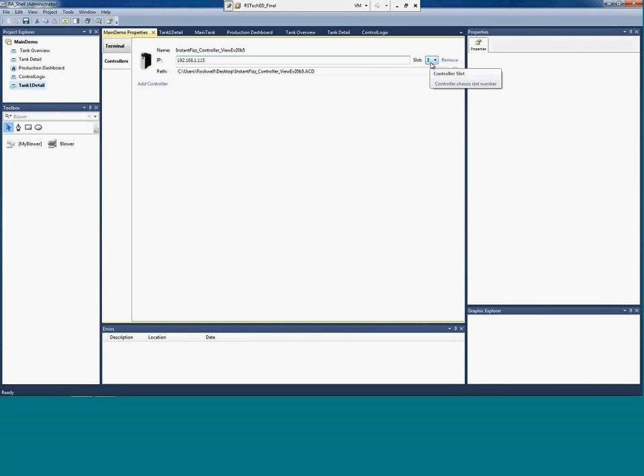You can associate either a single command with a touch event, or you can associate multiple commands with that event. And I'll pull down the command list that we have currently supported, just to show you some of the commands that we'll support. Commands like logging on and logging off for security. Navigation commands, so that you can touch an object and navigate to a different screen, as well as the value commands that we've just talked about, whether you're toggling a value, incrementing it, or writing a specific value to it. We'll also be adding additional commands to this as we continue to develop the product. So we'll have a command for switching languages on the terminal, or doing an alarm acknowledgement as an example. So we'll have a full list of commands available.